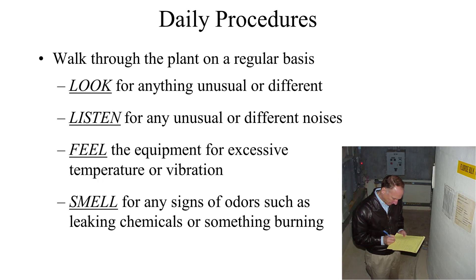Be aware of any odors — maybe something is burning or there is a chlorine leak. As an operator, walking through the plant every day, sometimes several times a day, I noticed that there was a certain feel to the plant when it was running well. And when I would take a walk through the plant and something was wrong, I was able to kind of track it down — it might have been a noise, something I saw, or an odor. One of the jobs of being an operator is to really know your plant.